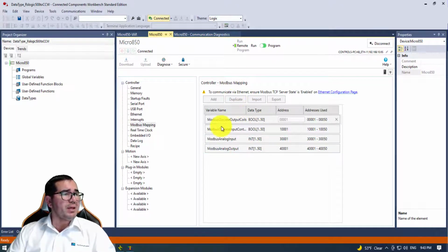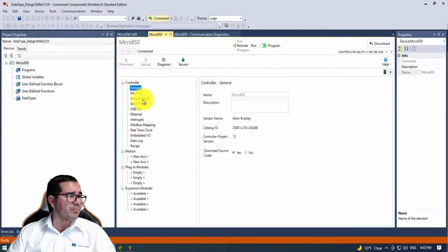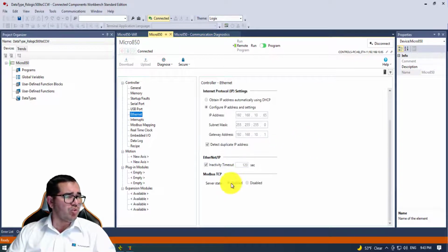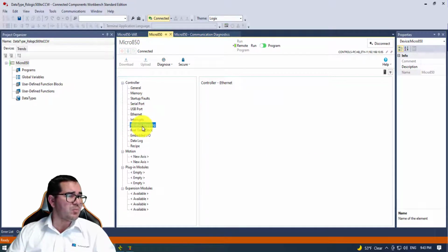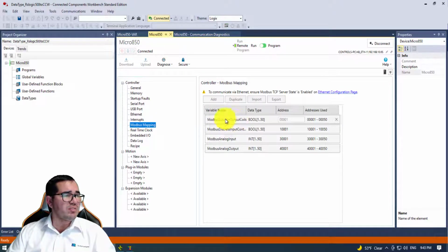So I mapped the Modbus TCP here, and after that you create it over here. Like I said, you need to do this offline first, in general or in Ethernet. You need to make sure that you have the Modbus TCP server state enabled, so check this first. Then go to Modbus mapping, add, and create these tags with these addresses, one by one.